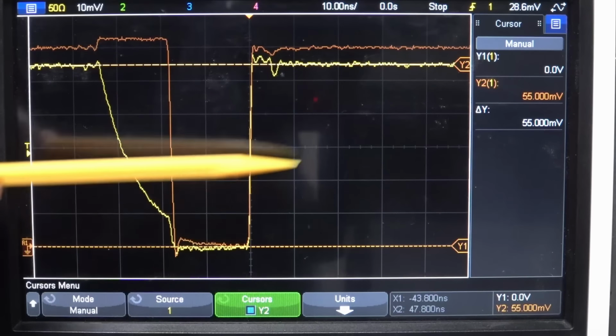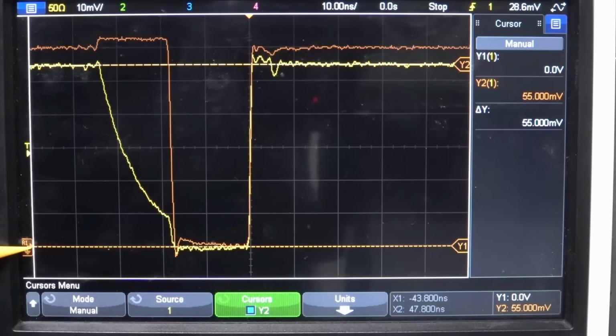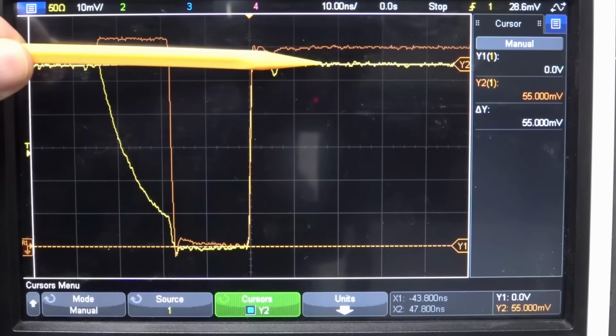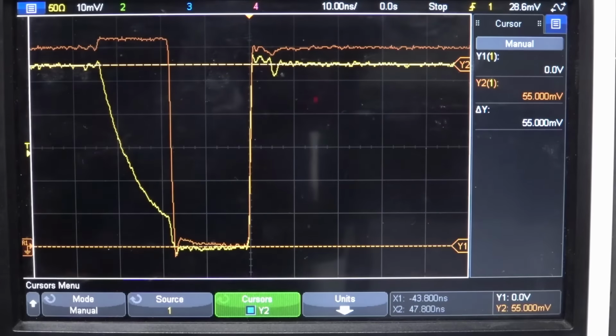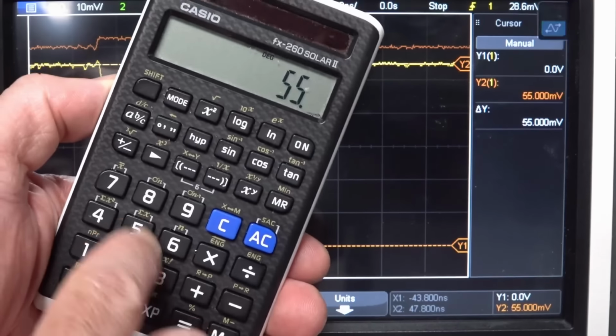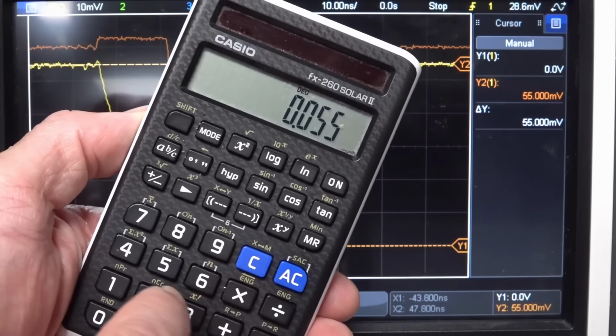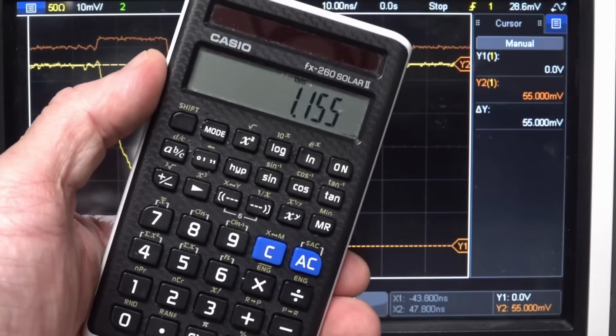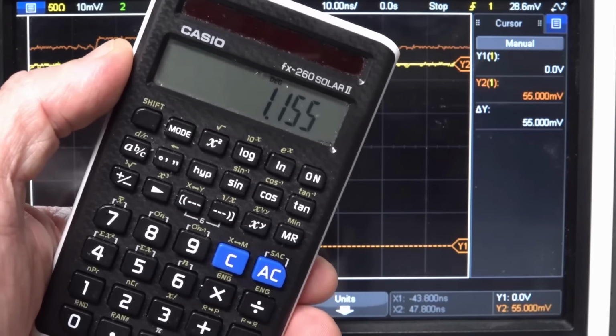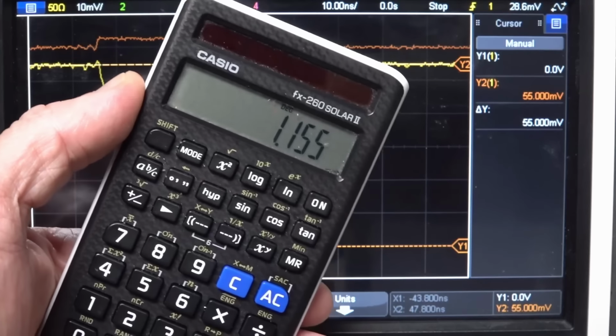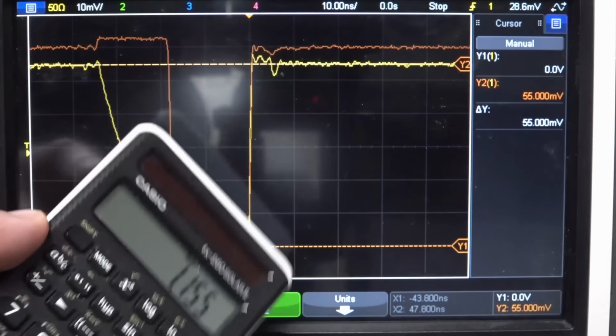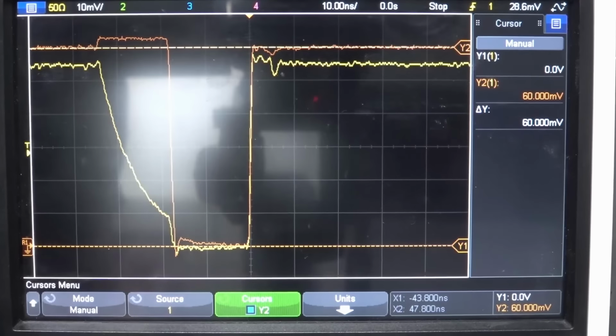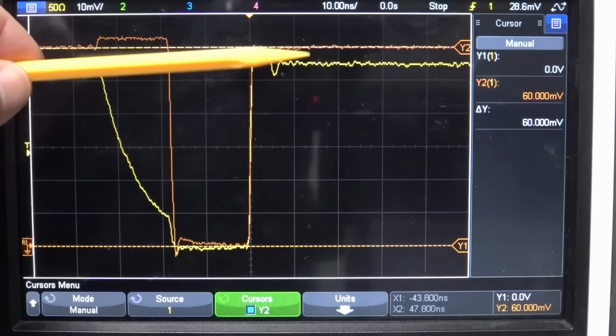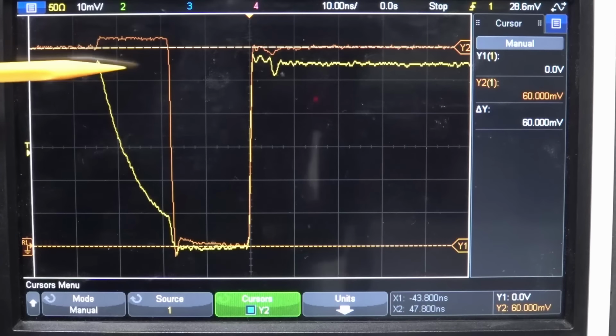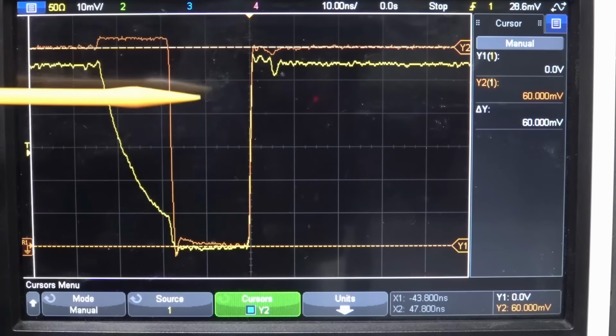So if we actually set up our cursors here, and I've set them precisely to the same ground point here. Our resistive probe, we're getting 55 millivolts there. So if you get your computer out, 55 millivolts times 21, which is our probe, 1.155 volts. And it looks like it's a 1.2 volt bus. So it's maybe 50 millivolts under, but we have to measure the other one actually. So if we adjust that, we're talking about 60 millivolts there. So it's actually precisely 6 divisions there, and we were on 200 millivolts per division, so that's precisely 1.2 volts.